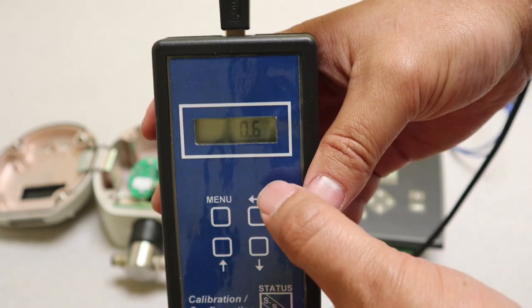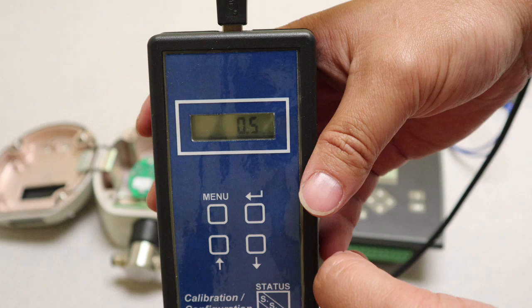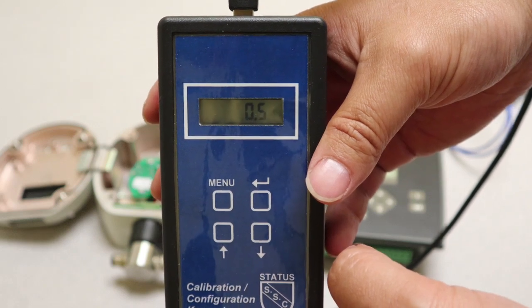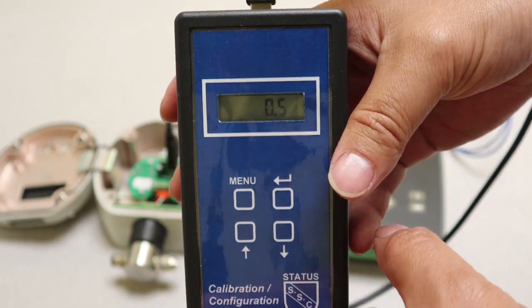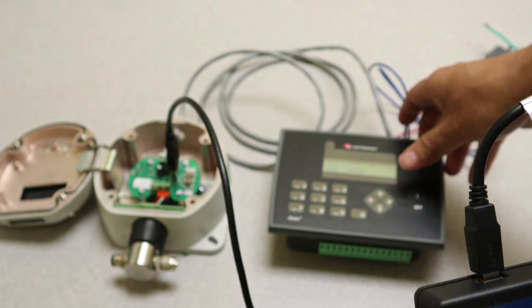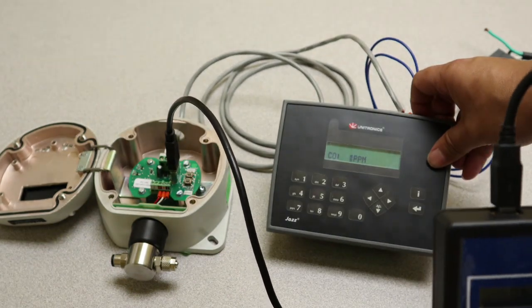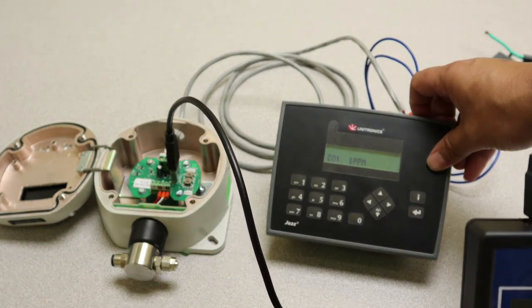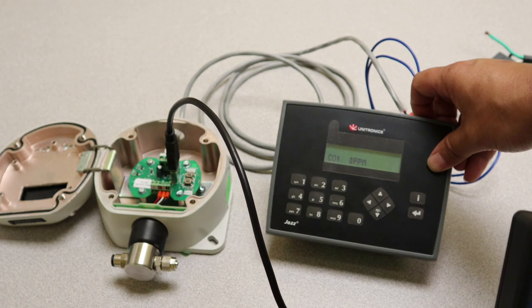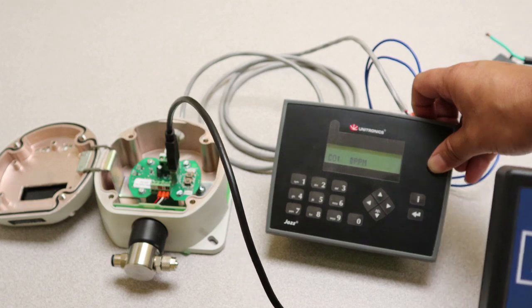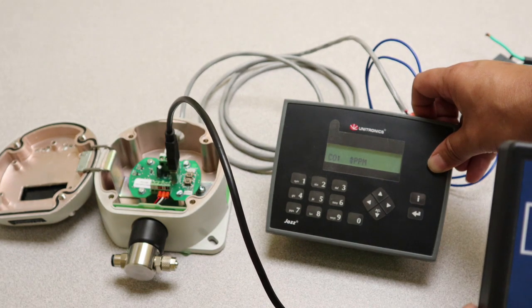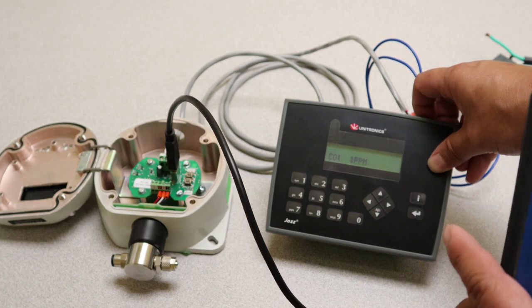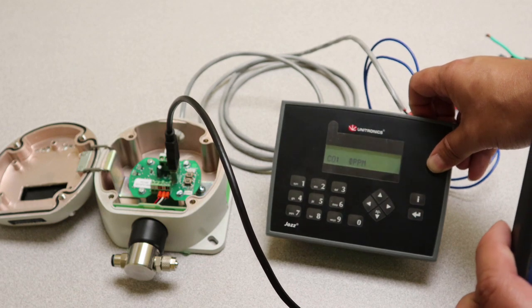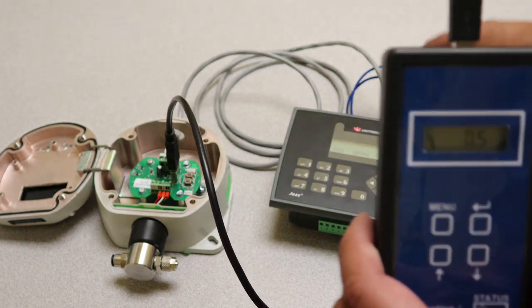Okay, so right now it's reading 0.6, 0.5 ppm of CO, which is a little bit off. And as you can see, our PLC is currently reading between 0 and 1. And that's what's causing the flash, is that it's actually reading 0.6 and 0.5. And 0.5 is being rounded to 0, and 0.6 is being rounded to 1. So it's going between 1 and 0. So we're going to do some calibration on this unit.